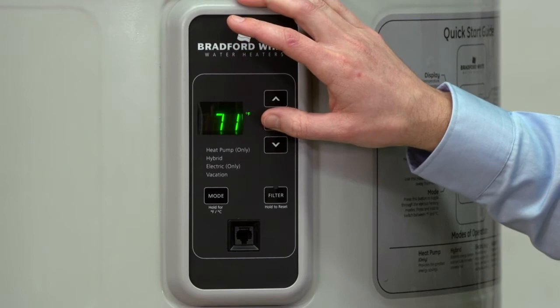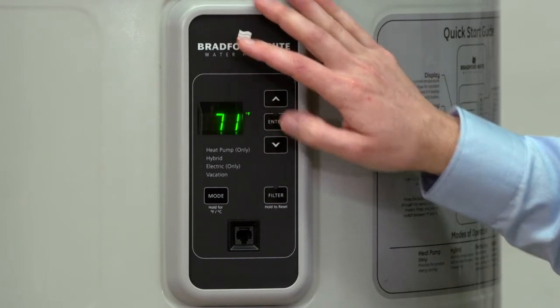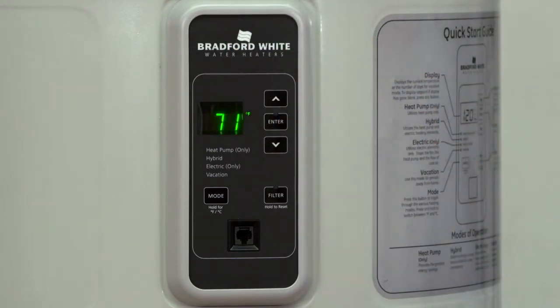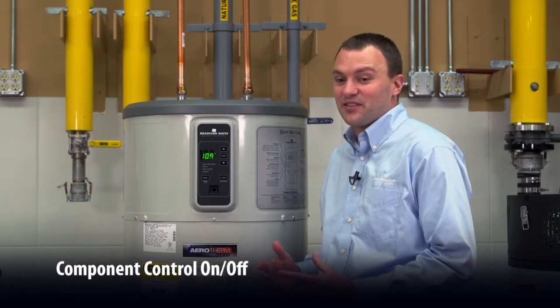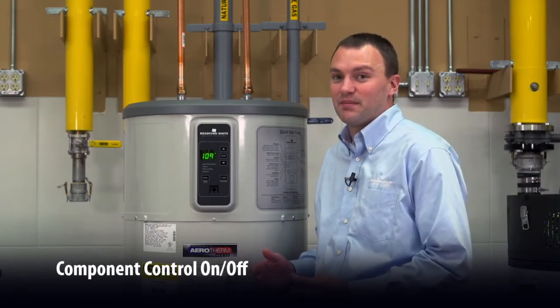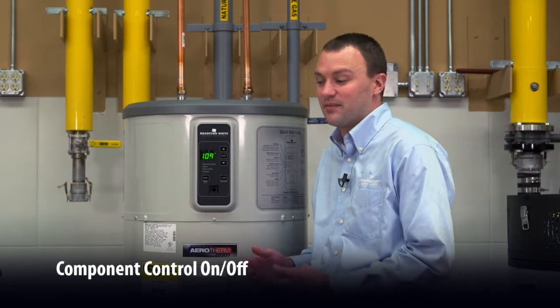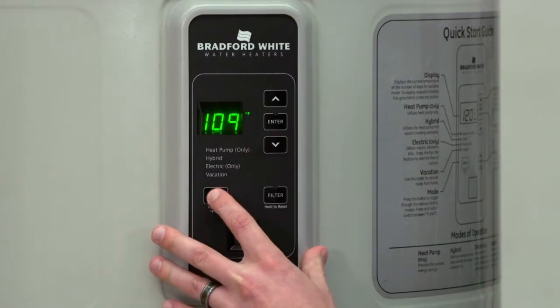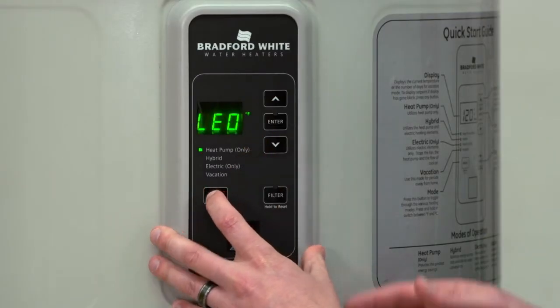So as a reminder, the temperatures we just saw are used as a reference. It may vary from location to location depending on the installation. The next capability I want to show you in service mode is the ability to turn components on and off in the heating system. So we're going to use the mode button.